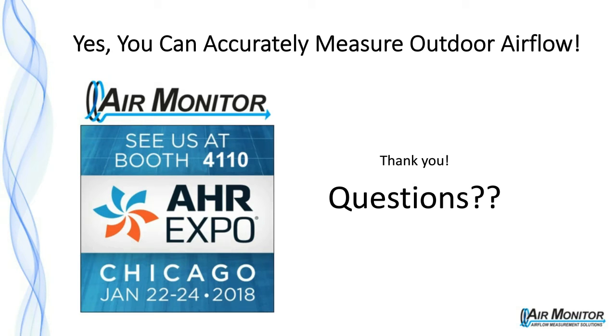Another question we just received discusses how many sensors are needed. Do we need multiple sensors based on the area? Do large louvers require multiple sensors? The answer is yes. There is more or less a design guideline of 30 square feet per sensing point. But as Matt brought up, when we're looking at big louvers, we need to make sure that all sections of the louver are controlled together, and that the louver is the same in terms of its characteristics across that range. In most cases they are, and when you have a large louver encompassing a large area, it's not uncommon to manifold 3 or 4 sensors together and bring those back to a single system or a single transmitter.